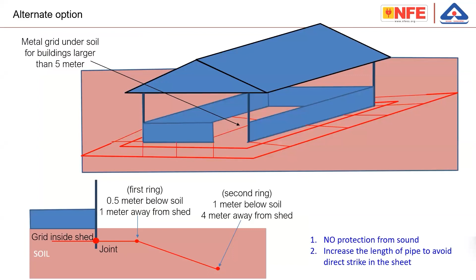Schools: be very careful to protect people outside schools and hospitals. It is not the strike which is killing, it is the step and touch potential and flashovers. Equally, they are also dangerous. In the area where people are standing, we are supposed to make additional ring conductors and make the area an equipotential plane. And the equipotential plane must be connected to the air termination at several intervals depending upon the standard. For example, level 1, 10 meters; level 4, 20 meters. So you have to make proper protection for these kinds of buildings.